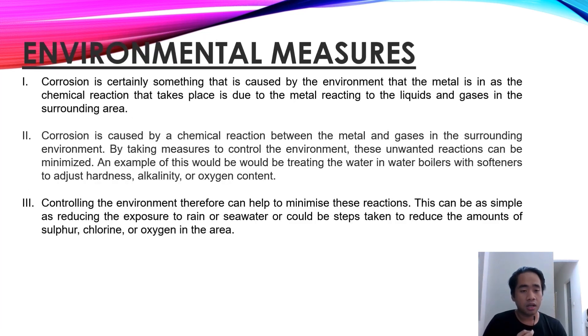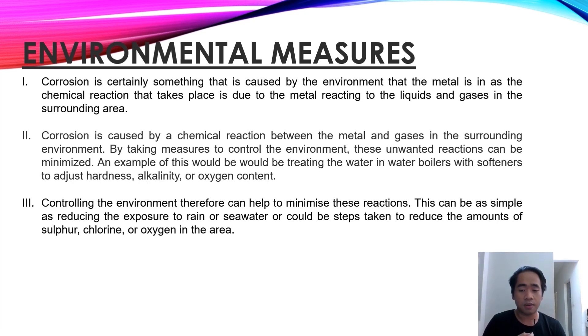The third prevention method is environmental measures. Corrosion is caused by the environment the metal is in, as the chemical reaction takes place due to the metal reacting to liquids and gases in the surrounding area. By taking measures to control the environment, this unwanted reaction can be minimized. An example would be treating water in a water boiler with softener to adjust hardness, alkalinity, and oxygen content. Controlling the environment can be as simple as reducing exposure to rain and seawater, or taking steps to reduce the amount of sulfur, chlorine, or oxygen in the area.